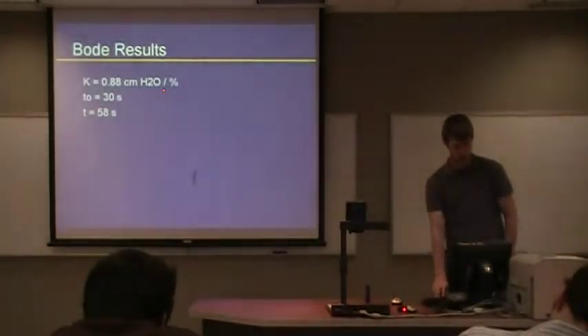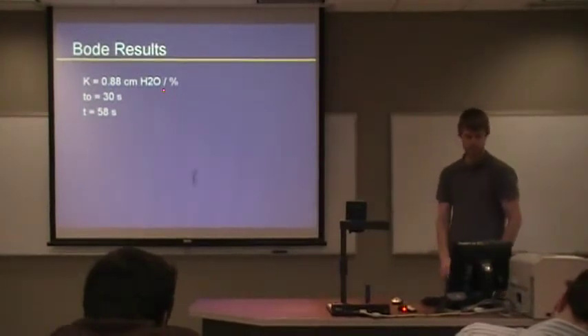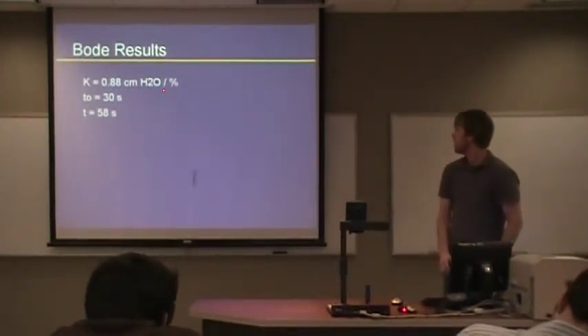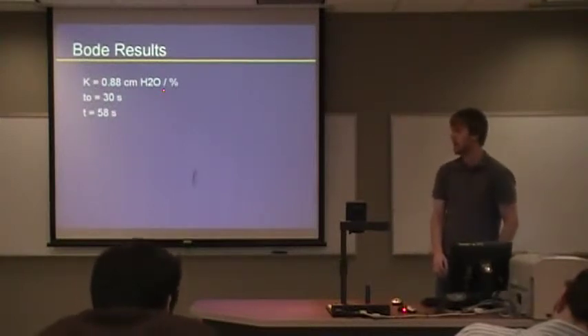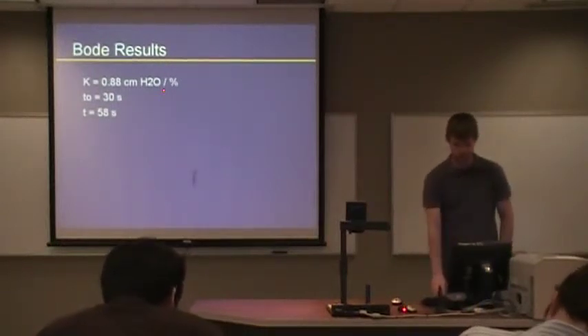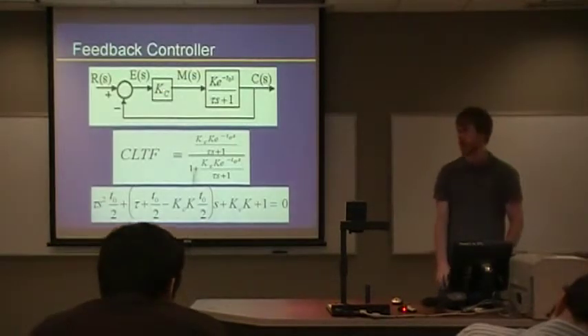Here are the situations a lot of times. And the results from the modeling that we got from the Bode. The K of the system of .88 centimeters water per percent. A dead time of 30 seconds. And a tau of 58 seconds, which all agrees with what we had from our steps.